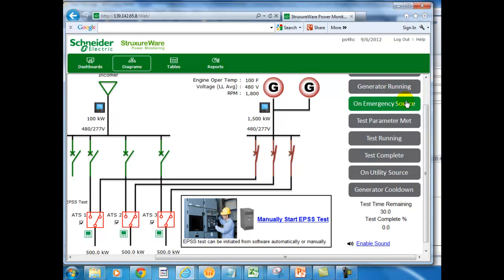Here we go. The test parameter met probably means the transfer switch operated within tolerance. There could be other parameters like how much load your transfer switch is carrying with respect to the nameplate ratings. That's another criteria. So this test is going to run for 30 seconds.